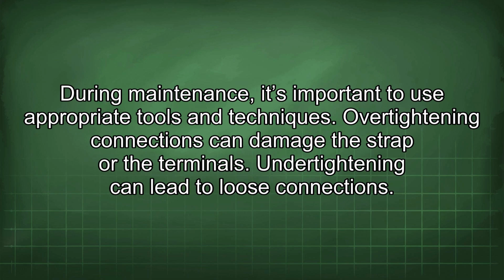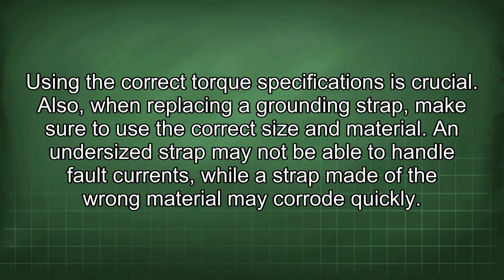During maintenance, it's important to use appropriate tools and techniques. Over-tightening connections can damage the strap or the terminals. Under-tightening can lead to loose connections. Using the correct torque specifications is crucial. Also, when replacing a grounding strap, make sure to use the correct size and material. An undersized strap may not be able to handle fault currents, while a strap made of the wrong material may corrode quickly.